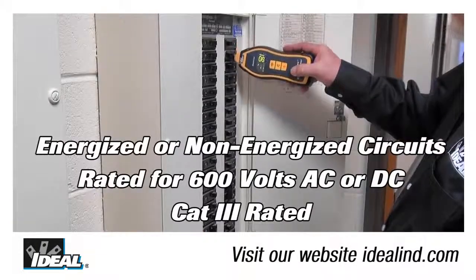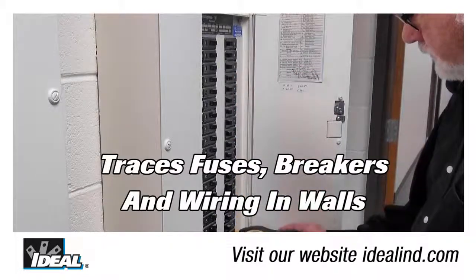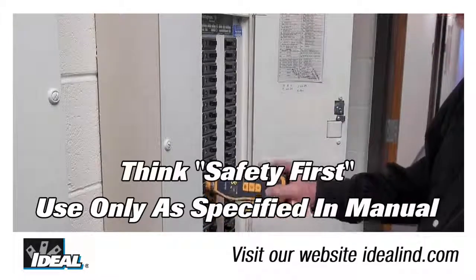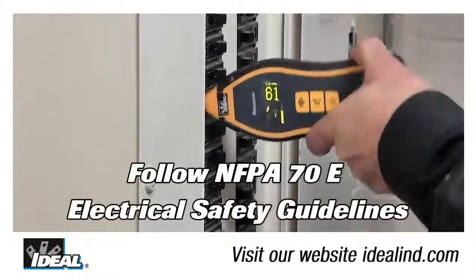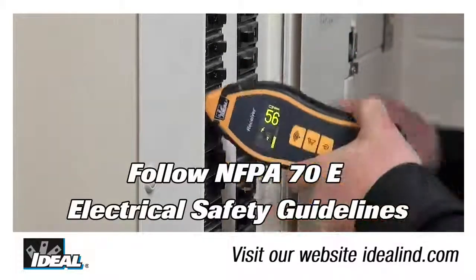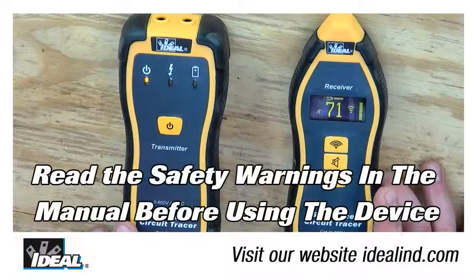The tracer can be used on either open or closed circuits and is rated for up to 600 volts AC or DC and is a Category 3 rated tester, so it can be safely used in distribution panels and throughout a building. Now, if you're using circuit tracers to trace live circuits, folks, please be safe out there and follow good industry safety practices. The tracers consist of a transmitter and a receiver.